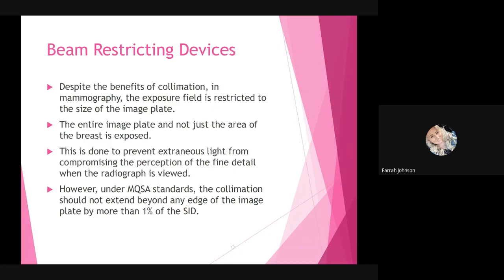This is done to prevent extraneous light from compromising the perception of the fine detail when the radiograph is viewed. However, under MQSA standards, the collimation should not extend beyond any edge of the image plate by more than 1% of the SID, and that is calibrated and measured when installing a machine.